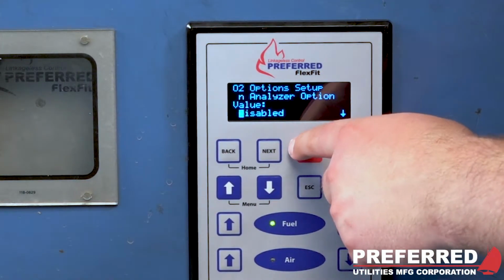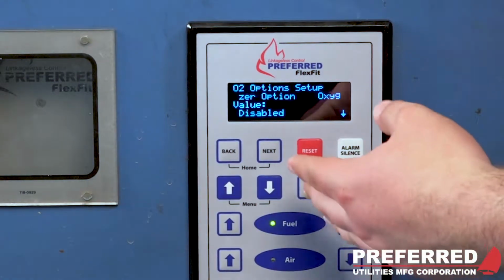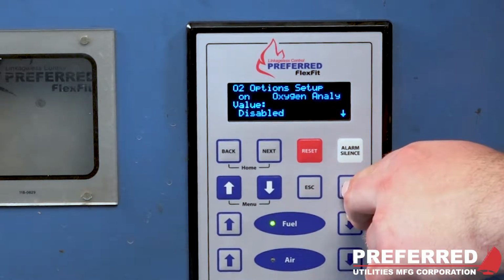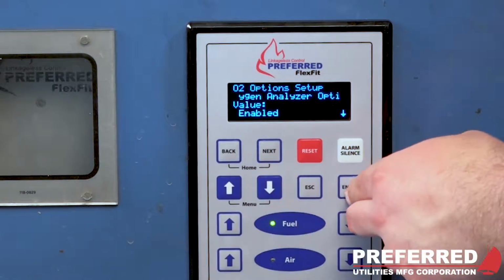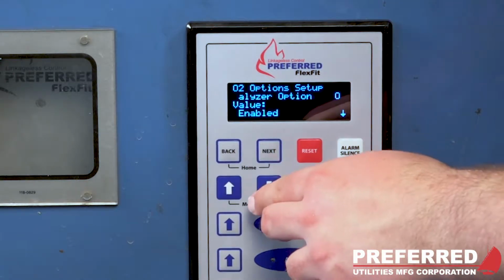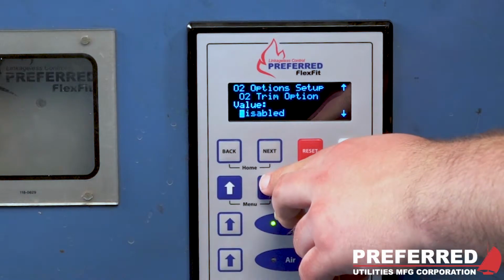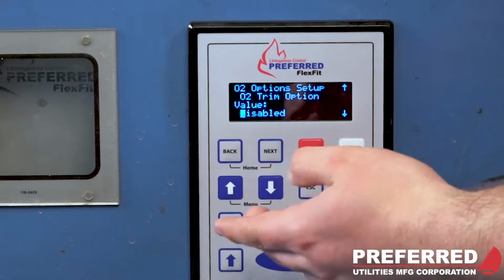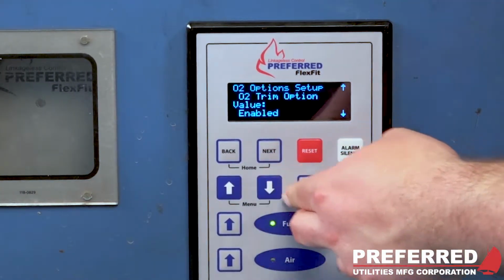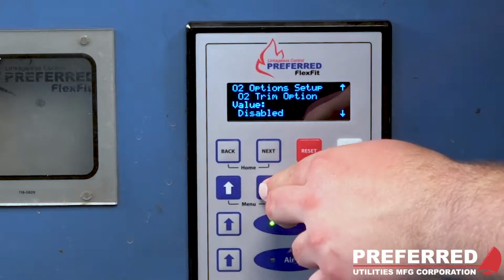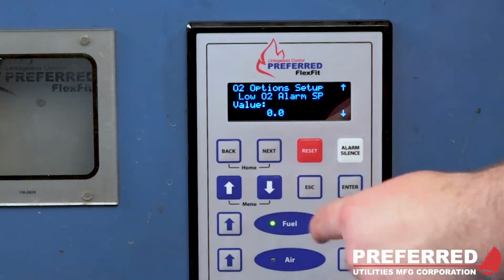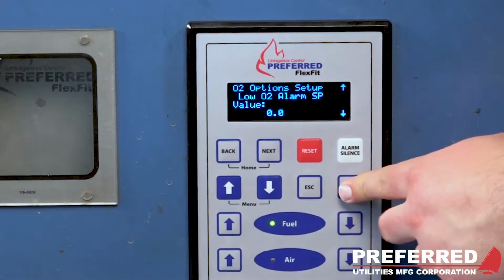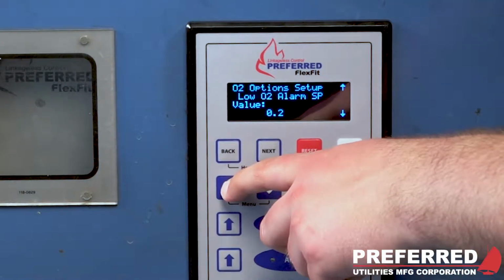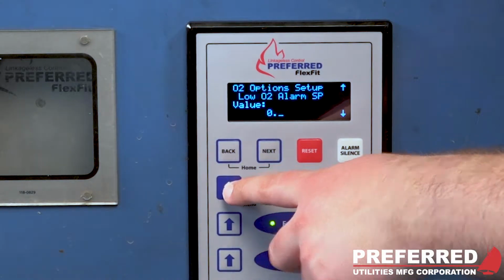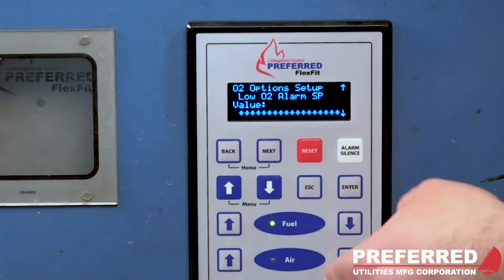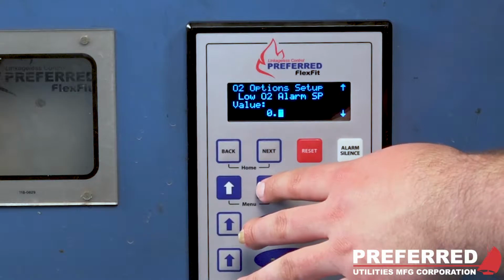And now it will say O2 Analyzer option. Right now it's disabled. You want to enable that because we are now using an O2 sensor. So you enable. If you want to use your O2 trim, because we are using the sensor now, we can enable that. And now we can set our alarm and lockout set points. So I'll go ahead and just set low O2 alarm to 0.8 or whatever you would like that alarm to be.